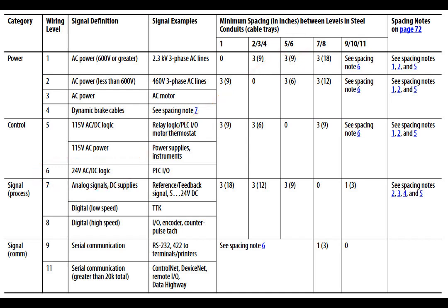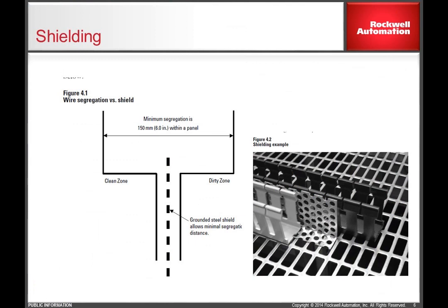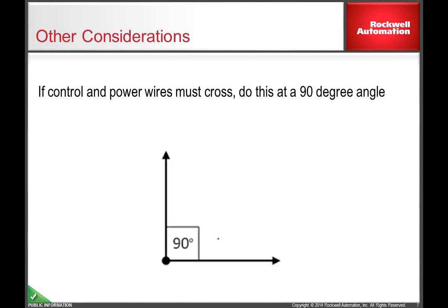In many cases, devices such as drives do not allow for these spacing restrictions to be met. In these cases, route the wire as far as possible and try to maintain these distances as best as you can. In some cases, it may be extremely difficult or impossible to meet the recommended spacing considerations. In these cases, it is recommended to use grounded shielding devices within the enclosure such as the Panduit shield shown, or use shielded or armored shielded cables. If cables of different wiring levels must cross, do this at a 90 degree angle. This will minimize any induced voltages from one cable to the other.